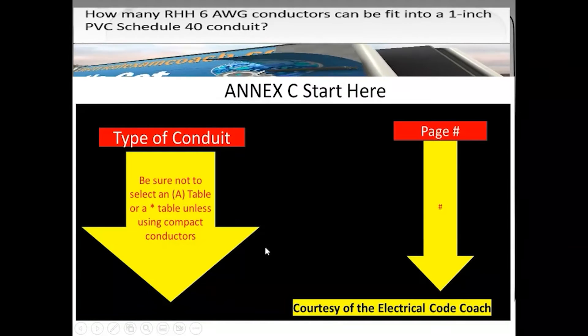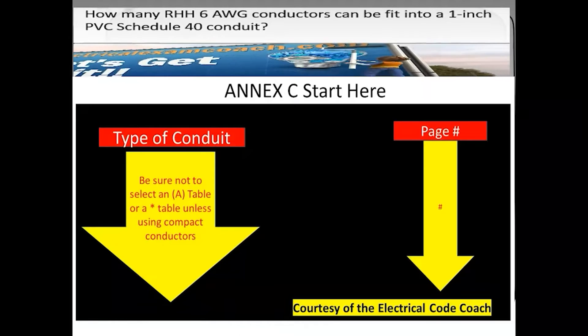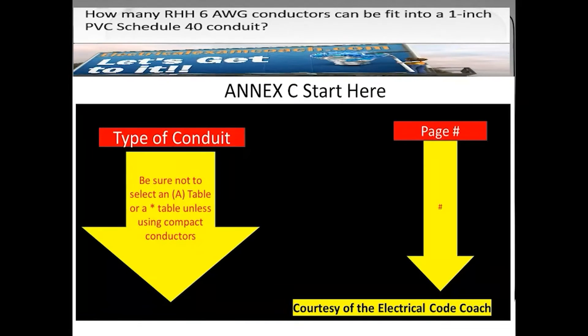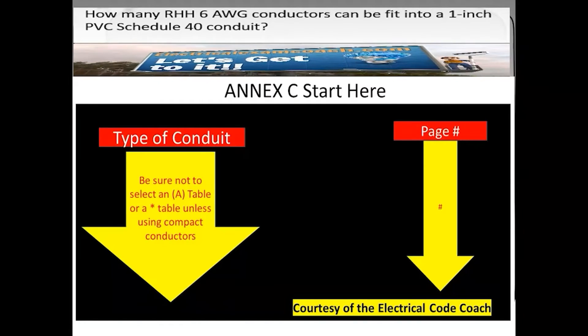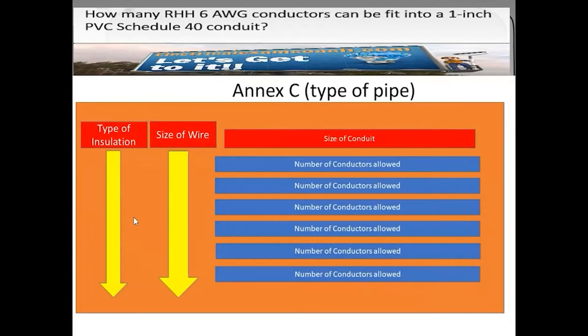We're going to head to our Annex C start-here table, which is at the very beginning of Annex C. We start on the left-hand side and find our type of conduit, come down, and come across the page into the page number column. Then we tee off with our page number and head there. When we get to the page, we start on the left-hand side and find our type of insulation, then come to our wire size, then come across the top to find our conduit size and tee off with the number of conductors that fit into this one-inch piece of schedule 40.